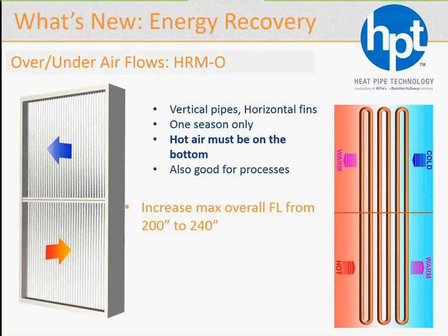Now, with this particular product, the overall height has increased from 200 to 240 inches. This is already incorporated in our selection program. Before, with a flag, it was limited, now you're able to do 240 inches. Of course, a gap extension applies to this product as well. It went from 8 to 40 inches. Caution again with what we said earlier: extended drain pans will be needed in condensing air streams.